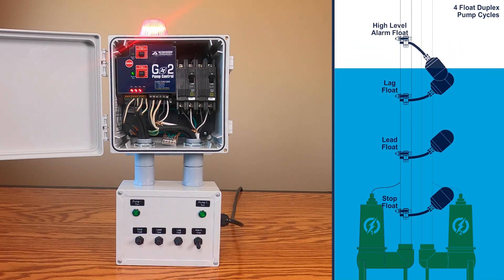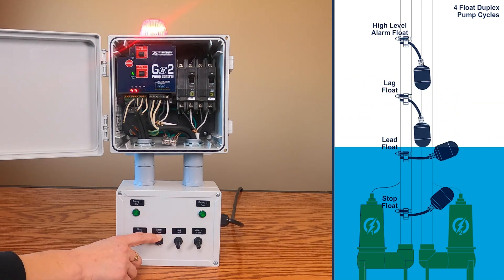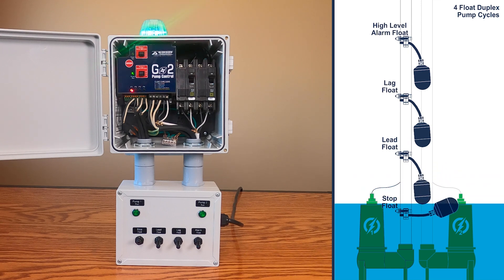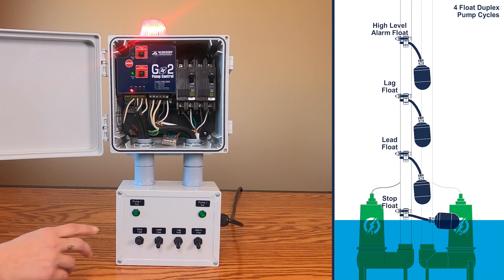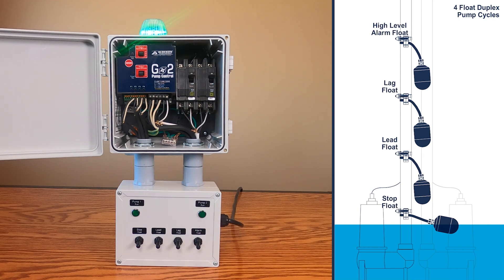The water level will lower and the alarm float will tilt down. As the pumps continue lowering the water level, the lag float will tilt down, then the lead float will tilt down. Notice the pump and alarm beacon will remain on all the way to the off float, at which time the pump and alarm beacon will turn off. This completes the alarm pumping cycle. Note the alarm is automatically reset and the beacon glows steady green indicating normal operation. This completes our demonstration for the GO 2 duplex control panel demonstrating float controlled pumping cycles. Thanks for watching.